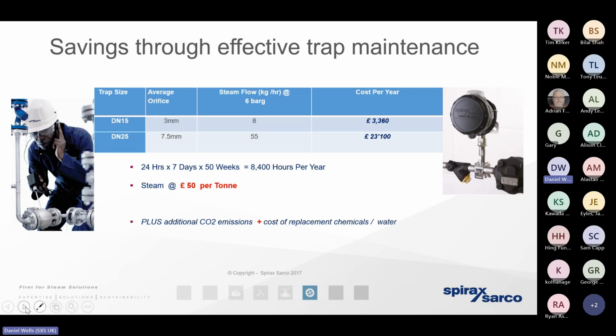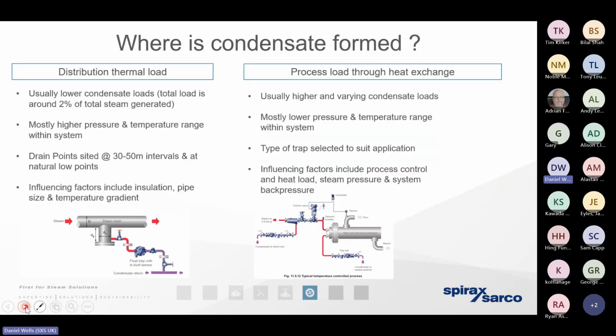And remember, we could have multiple traps on site that are failing. So it reminds us why steam trap engineering is one of the biggest and one of the quickest wins when it comes to ensuring that our steam system is operating efficiently. And it also reminds us why our client is going to want that periodic steam trap survey in order to ensure that those traps have been correctly installed, engineered, maintained, that they're not failed, that they're selected correctly. And in certain applications, our client may wish to move towards some form of automation to instantly understand if and when that trap has started to move towards a failed condition.